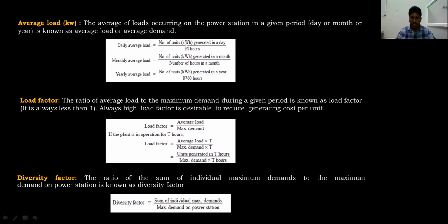1 kilowatt hour is equal to 1 unit. Generally, at home we say 1 unit. So 1 unit means 1 kilowatt hour divided by 24 hours. This time and this time are the same and will cancel, and finally the result is in kilowatts. So average load is always in kilowatts. Average load is equal to the number of units generated in a day divided by 24 hours. For example, if it is a monthly figure, 24 hours into 30 days. If it is a yearly figure, 24 into 365 days. The total gives you the yearly average load.